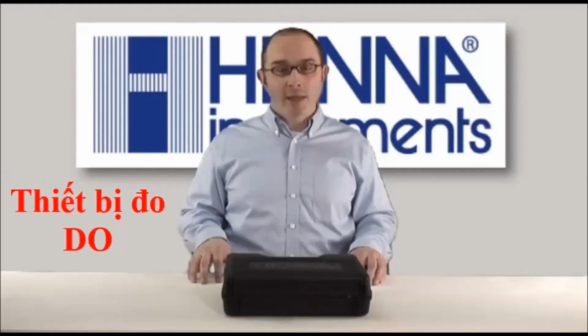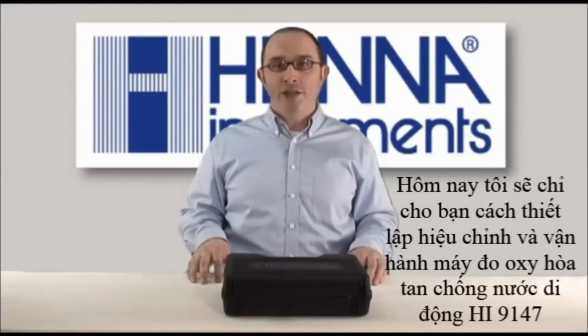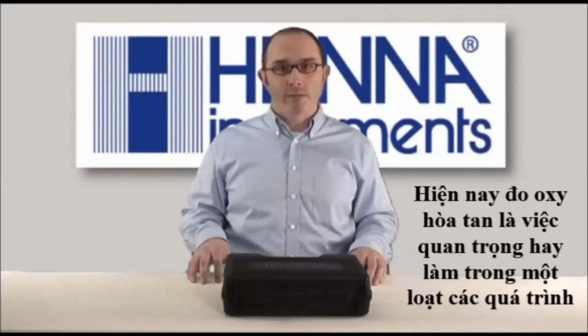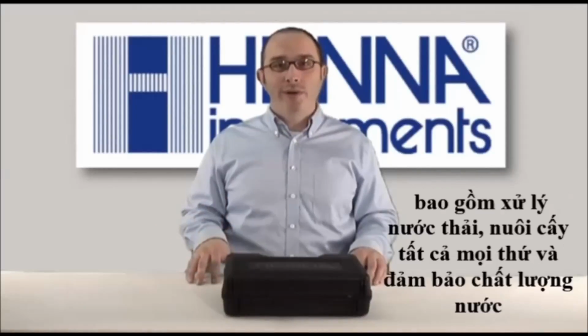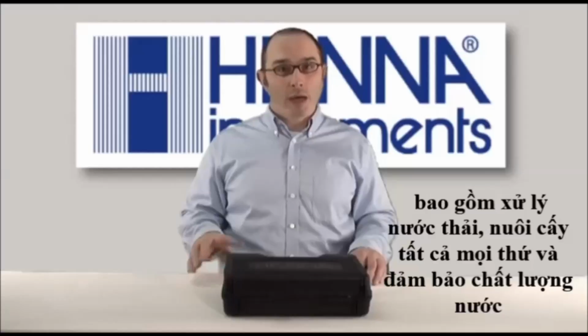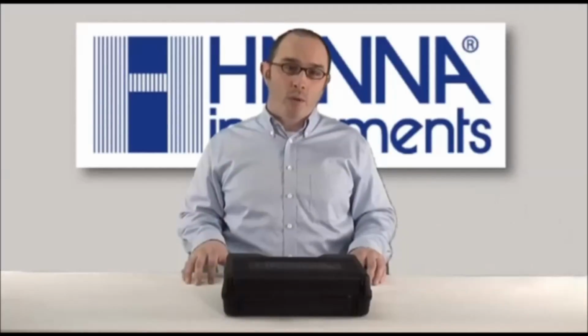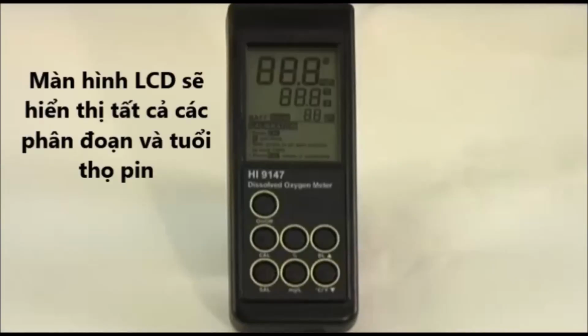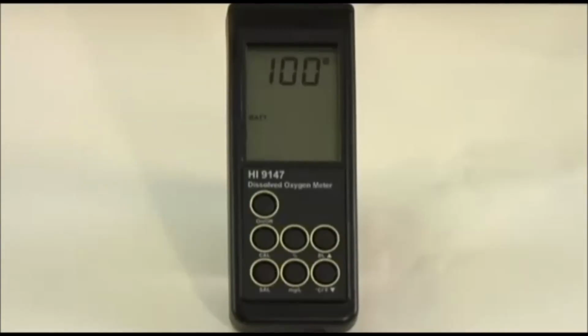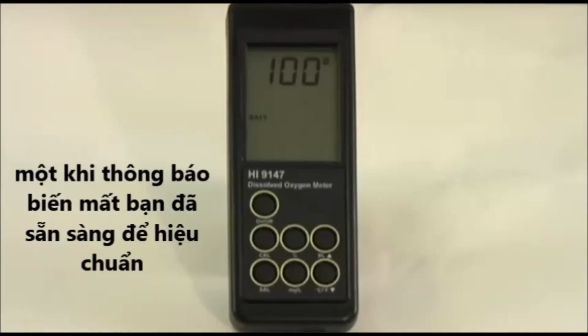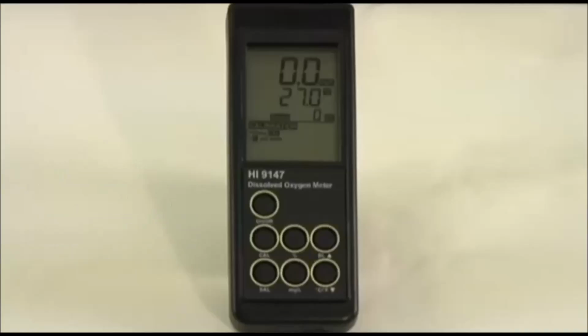Today I'm going to show you how to set up, calibrate, and operate the HI9147 Portable Water-Resistant Dissolved Oxygen Meter. Now, measuring dissolved oxygen, or DO, is important in a variety of applications, including aquaculture, beverage analysis, wastewater treatment, and water quality. The LCD display will show all of its segments and then indicate the battery life. Since this is a galvanic probe and meter, once the message disappears, you're ready for calibration.